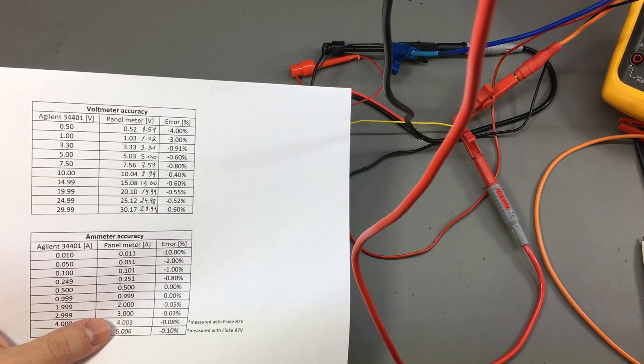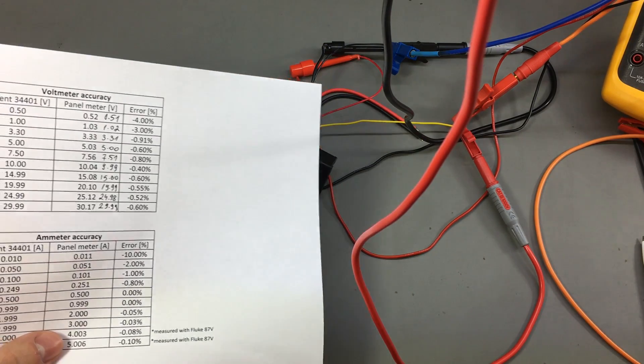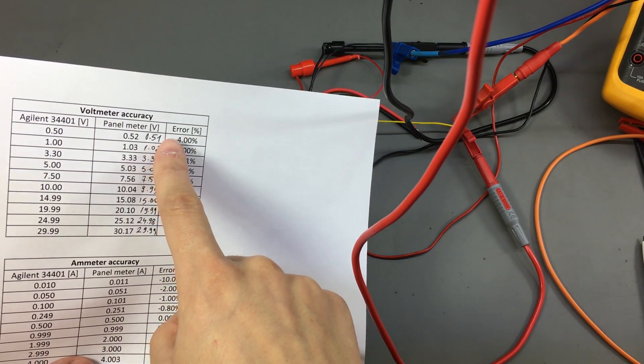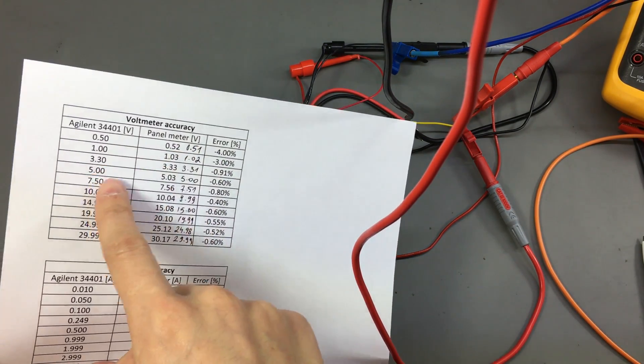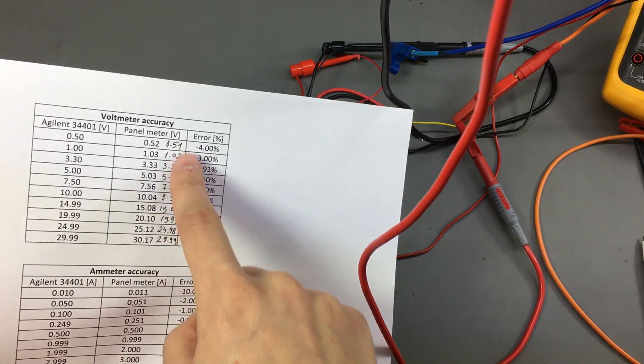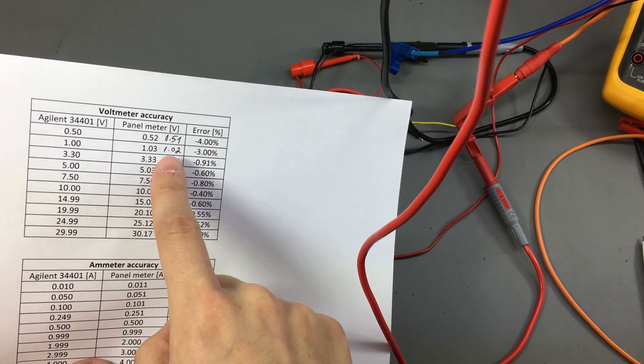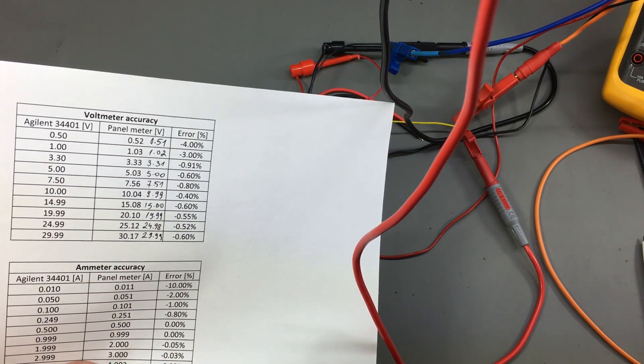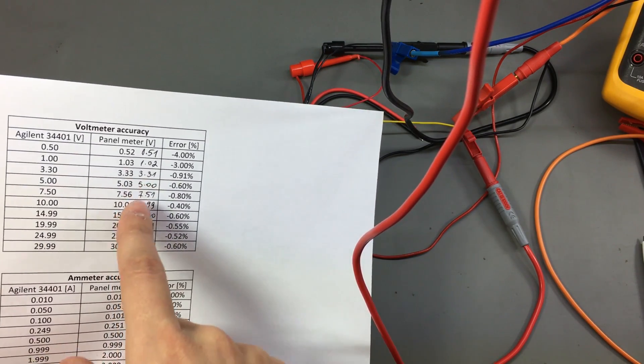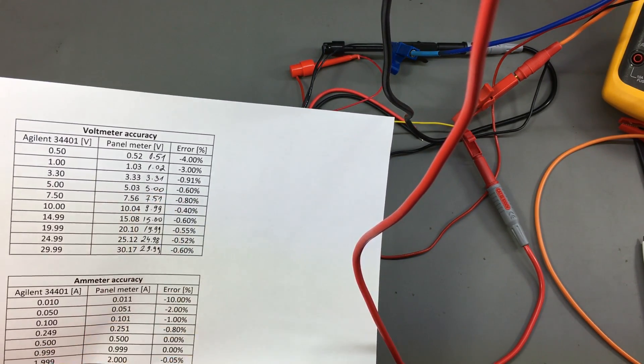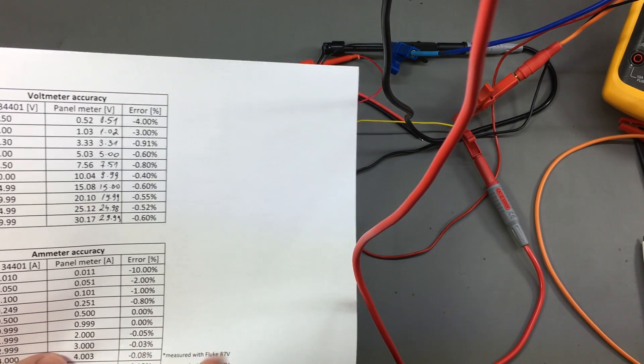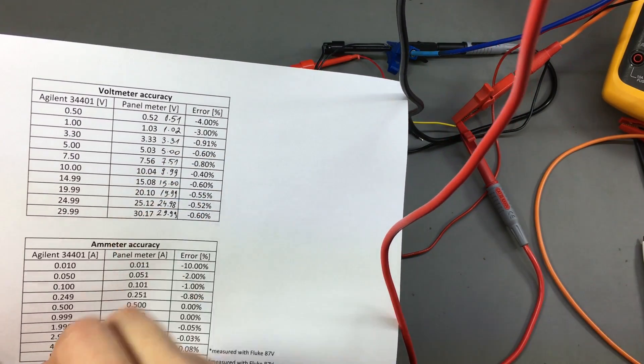But I got some interesting results after adjusting. It is only 1 count or 2 counts out of the Agilent measurement. So after adjustment we are basically within the specified error. Sometimes with just these 2 decimal points it's 0% error, so pretty good accuracy after adjustment.